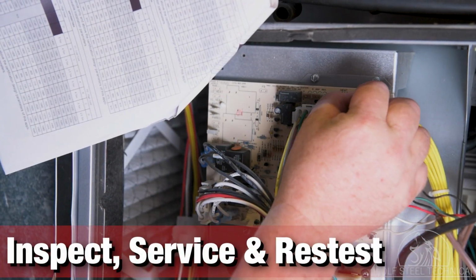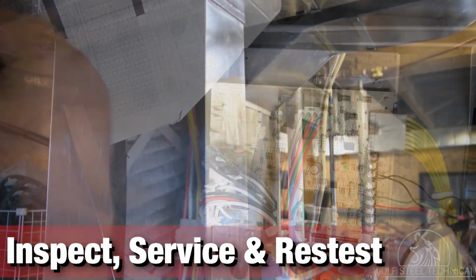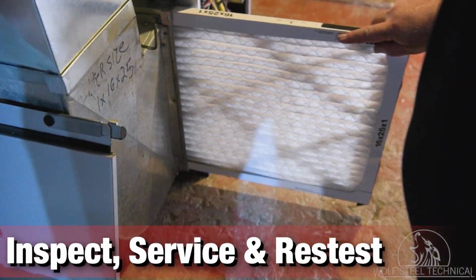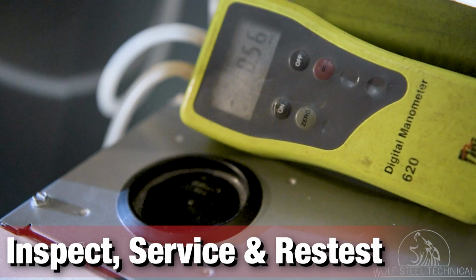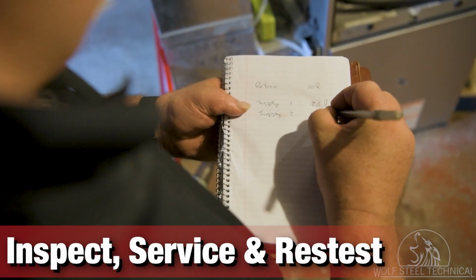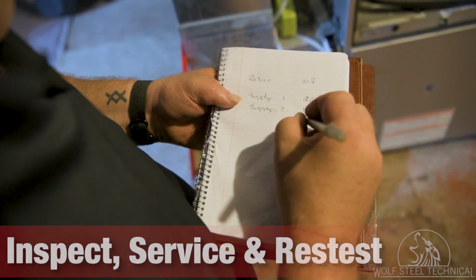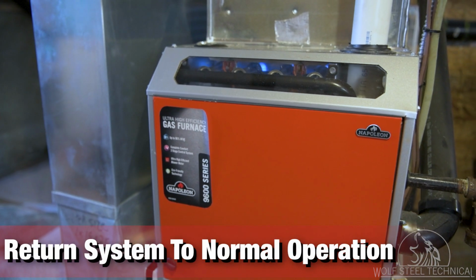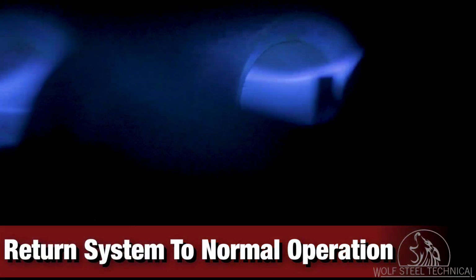It is important to inspect and adjust the fan speed, duct sizing or system cleanliness as needed, and re-perform the static pressure calculation to ensure that the system is operating efficiently. Once the static pressure is within an acceptable range, return the system to its normal operating mode before leaving it with your customer.